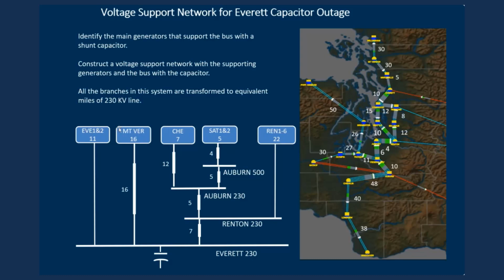In each side of these generators, we're showing you the actual equivalent line length of its step-up transformer. And then we take those values and we merge them with the actual values of the transmission lines themselves, and we build this, we call this the voltage support network. We only include those generators that are close electrically to the shunt capacitor that we're looking to remove or add, and we build this voltage support network, which you can see is a lot simpler than the real network.